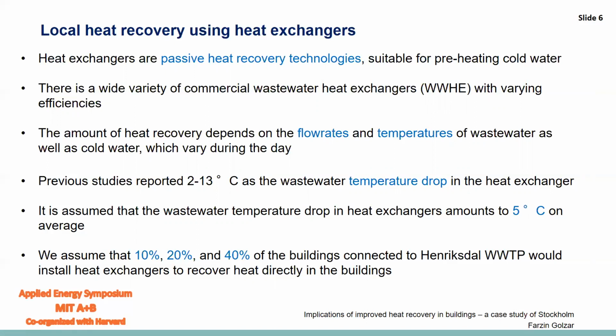A range of 2 to 13 degrees centigrade is reported in the literature, so we assumed an average value of 5 degrees centigrade as the wastewater temperature drop in the heat exchangers. We also assumed that in future, 10%, 20%, and 40% of buildings connected to the Henriksdal wastewater treatment plant would install heat exchangers for the purpose of wastewater heat recovery.